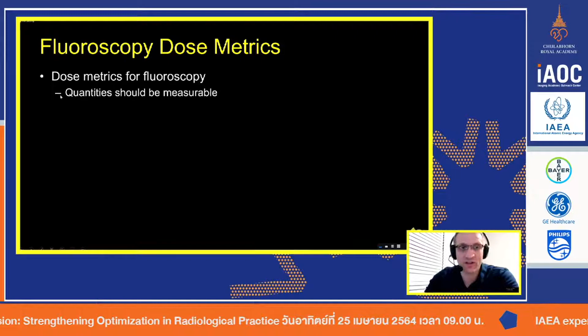As we said even last week with image quality, the metrics we use must be something that is measurable. And so it's the same concept here. We can't necessarily pick metrics such as effective dose or others that you can't physically measure with an ion chamber, because we can't validate them on the machine. So the first and most important aspect of any dose metric we use for fluoroscopy is that it's measurable.